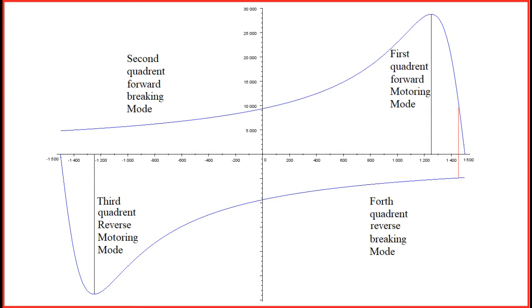When torque reaches maximum value, motor reaches certain speed as shown in first quadrant. Beyond this maximum torque position, characteristics is linear or a straight line characteristics. This is a normal portion where motor responds to changing load from no load to full load. This linear portion of characteristics curve is a stable portion and is similar to shunt motor characteristics.